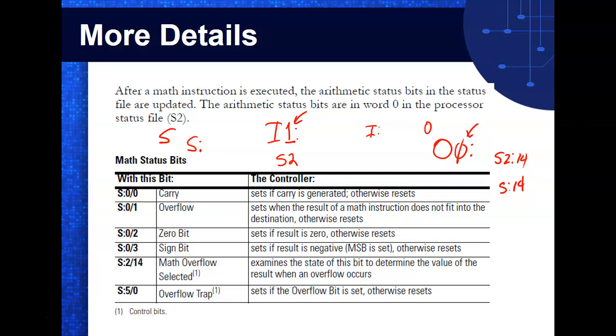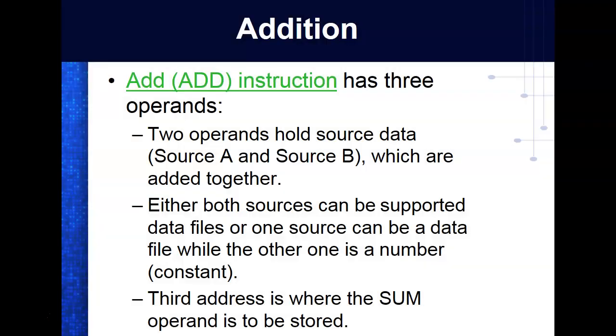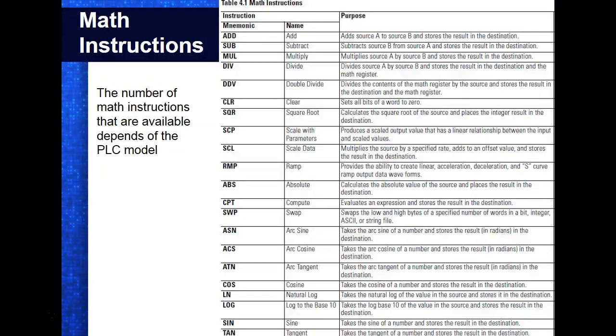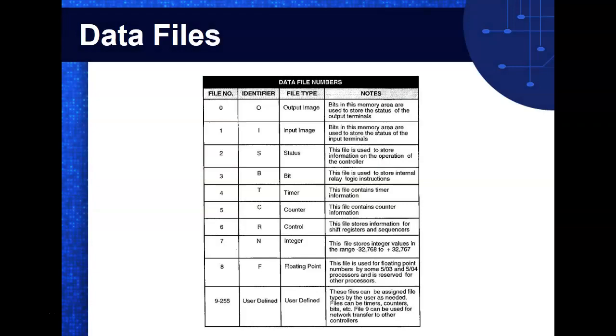So what I'm saying is that if I don't use any floating point numbers, then by George, on an RSLogix 500 machine, I am still losing all this space right here for floating point numbers, even if I don't use them, because the application is managing the memory, right? You understand? If I don't have any timers in my program, I still lose that memory, right? For 256 timers, that's 3 words of memory, 3 elements, for every timer. So how much memory are we losing? We're losing 3 times 256, even if we don't use timers.